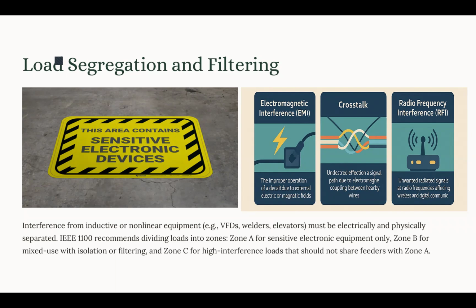Zone B, the second zone, is mixed use loads. Those panel boards supplying a mix of sensitive equipment and general equipment are considered zone B, but they have some mitigation measures too. An isolation transformer is required for these zones, to electrically separate the sensitive equipment from the noisy loads. We should have EMI filters installed on nonlinear or inductive loads within the same panel. And we should have physical separation of the circuits, so all the sensitive equipment is routed separately from the high interference circuits.